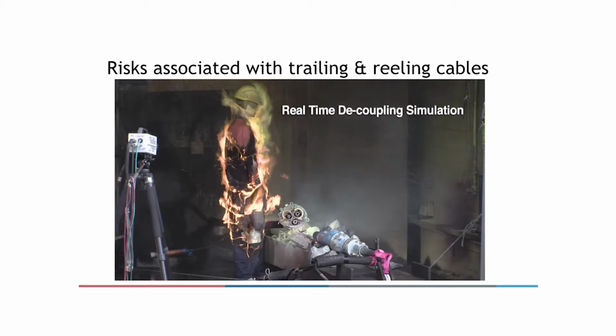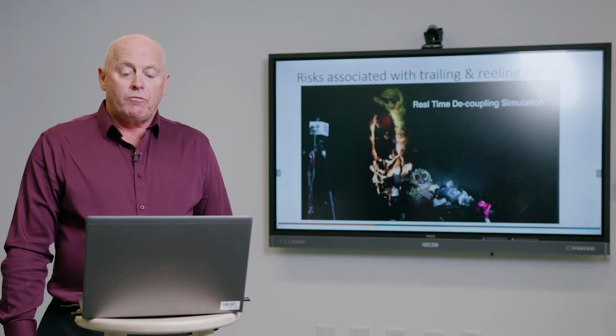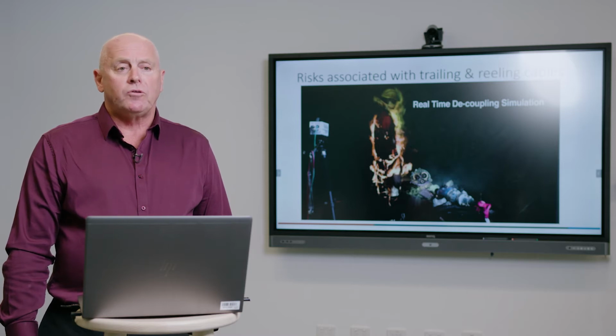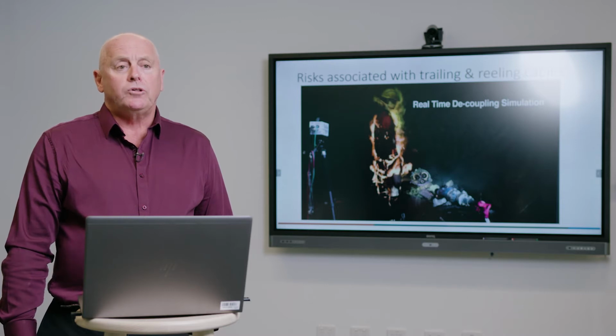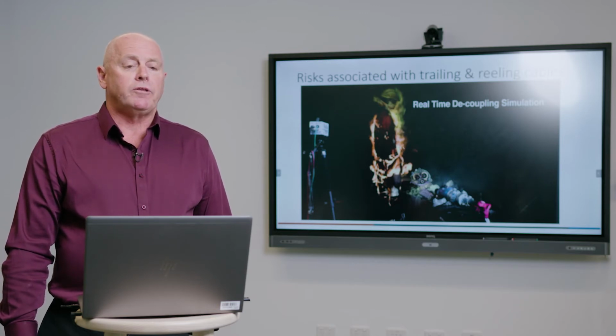This photo is from testing that BMA did at Lane Cove in New South Wales. They put this presentation together for a cable awareness package that they have developed. There's a lot of energy near trailing cable. Typically in open cut mines, these are 6.6, 11 or 22 kV. In an underground coal mine, these are typically 1,000 to 3,300 volts. Remember that the overhead power lines that you see outside your house are typically low voltage 415 volt conductors. Would you touch these conductors? Basically, trailing cables are overhead power lines with a bit of rubber insulation around them.